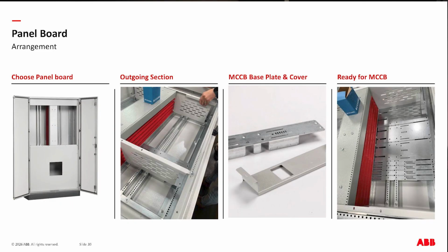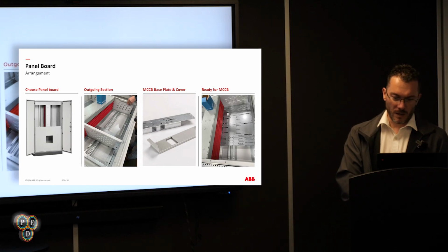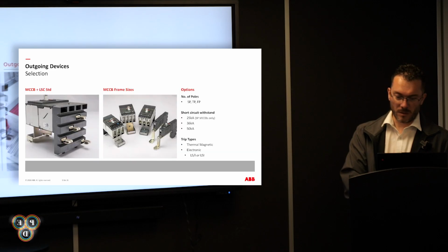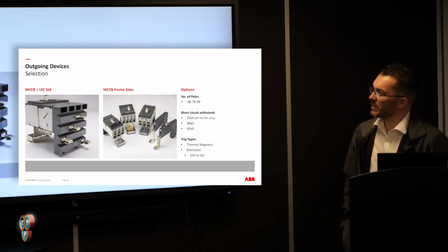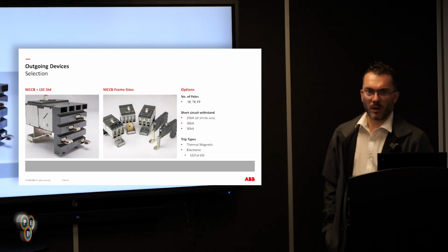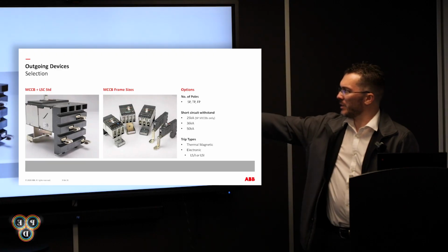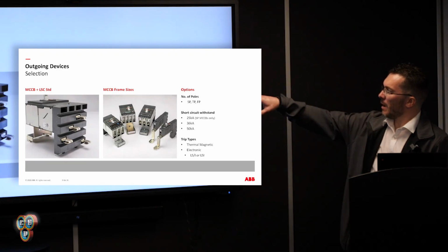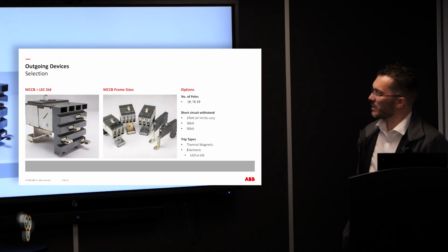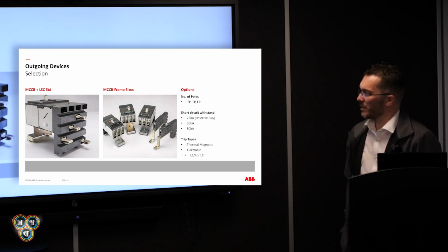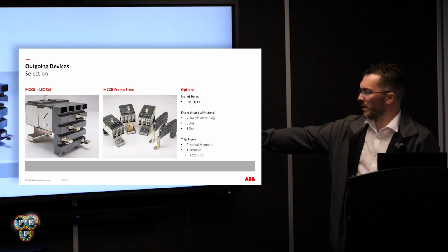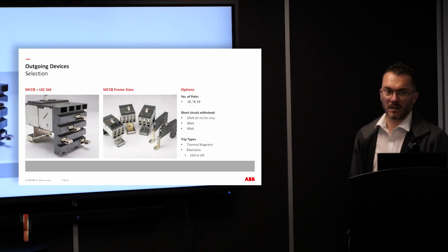One of the benefits we've got now is that all of our MCCBs for the Protector Power Panel Board are in a pluggable configuration. We now have that as an offering with a touch-proof busbar system there. As you can see from the devices, similar sort of design and layout. But we offer them in 25, 36 and 50 in single pole, triple pole, 4-pole devices, or there's the option of a separate neutral in thermal mag or electronic LS/I or LSI.